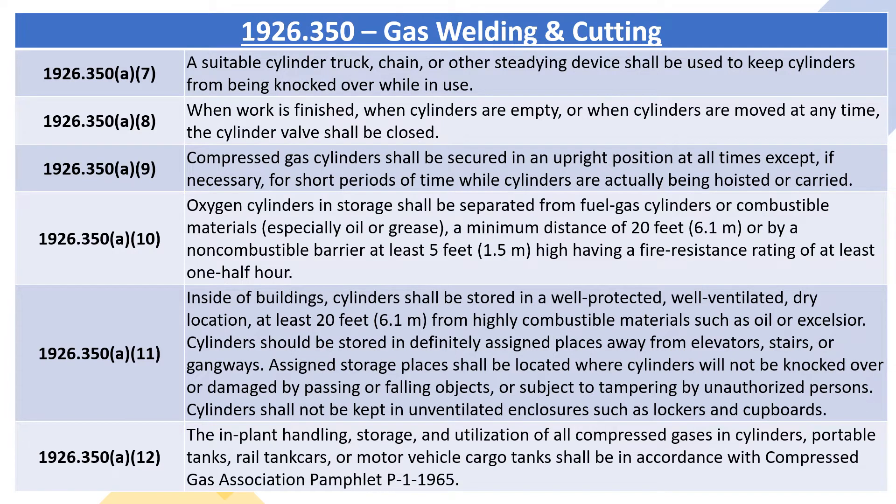1926.350A10: oxygen cylinders in storage shall be separated from fuel gas cylinders or combustible materials, especially oil or grease, a minimum distance of 20 feet (6.1 meters), or by a non-combustible barrier at least 5 feet (1.5 meters) high having a fire resistance rating of at least one-half hour.